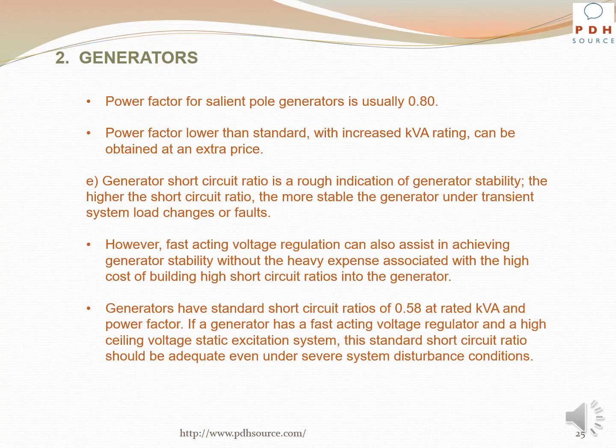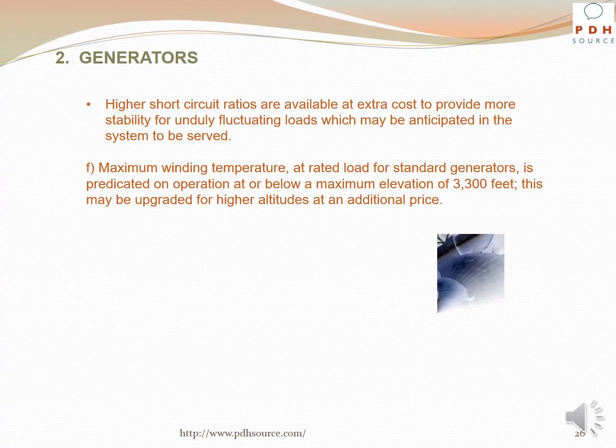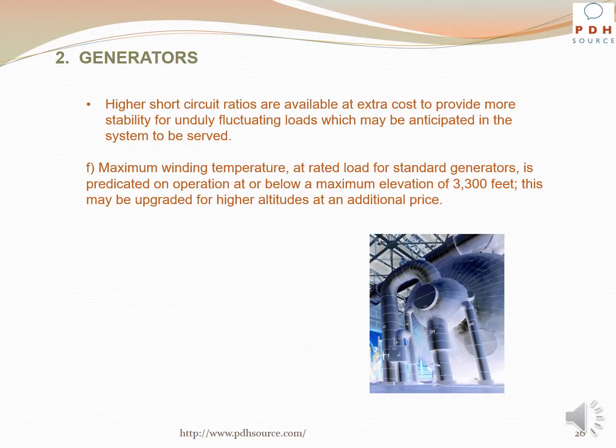Generators have standard short circuit ratios of 0.58 at rated kVA and power factor. If a generator has a fast-acting voltage regulator and a high ceiling voltage static excitation system, this standard short circuit ratio should be adequate even under severe system disturbance conditions. Higher short circuit ratios are available at extra cost to provide more stability for unduly fluctuating loads which may be anticipated in the system to be served.